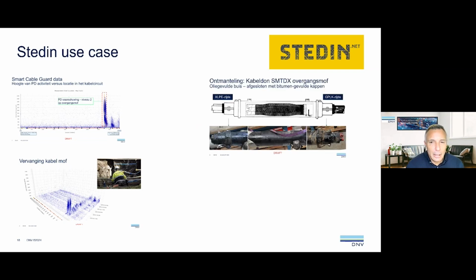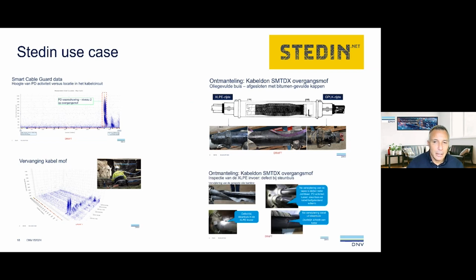They then sent us the joint for investigation. We have a lab where we do these investigations, so we investigated it and saw very clear signs of partial discharge. If you look at the picture on the lower right, you see almost 1 centimeter of partial discharge on the cable.